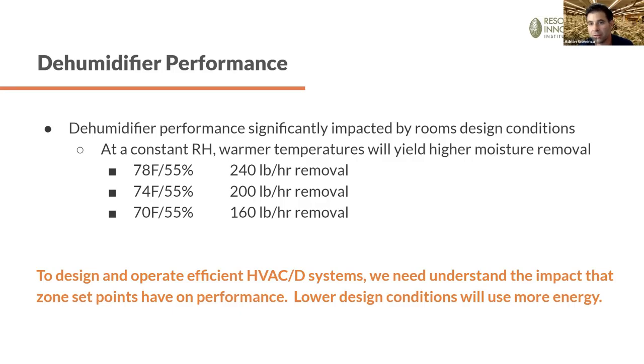It's really a balance. Just think if that was 70 degrees, 50% relative humidity, or 70 degrees, 45% relative humidity — that number, that 160, really drops drastically. That's why we see so many facilities that are either way oversized, because the numbers weren't really known and there was a lot of guesswork and extra safety factor, or most often what we see is that they're significantly undersized and not able to maintain the VPD they want in that space for the plants to thrive.